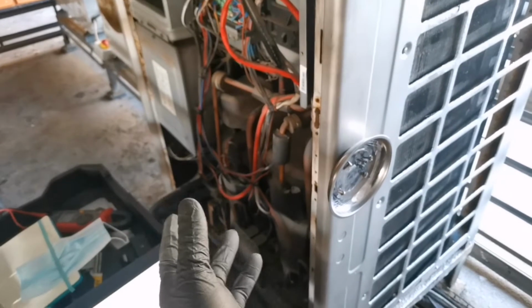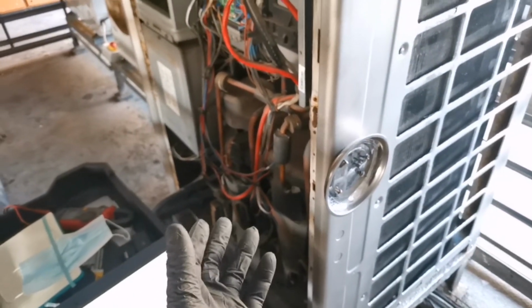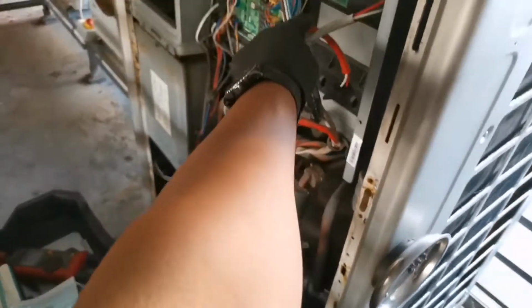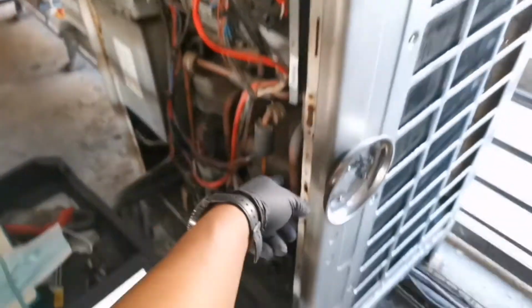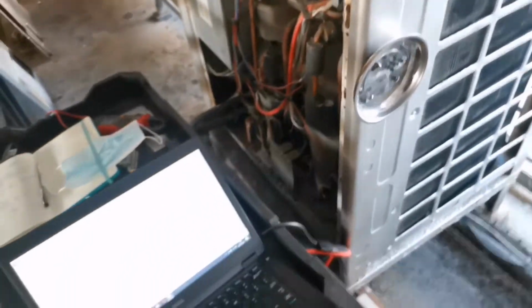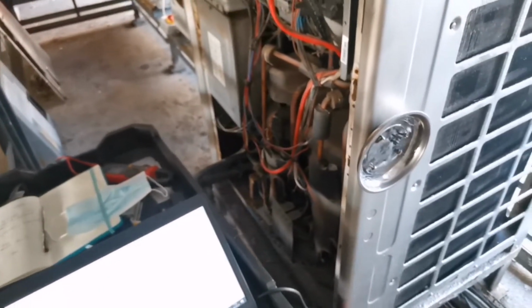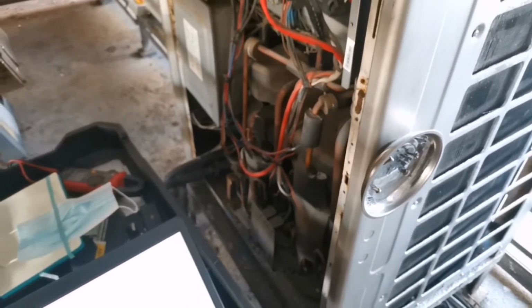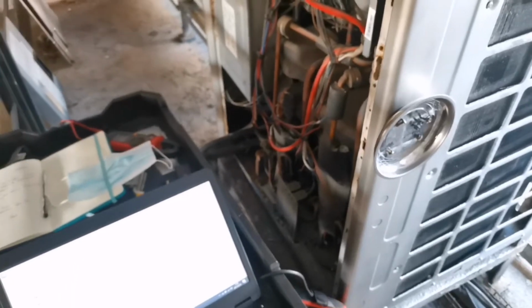So when they're using this system, for the first couple of minutes it seems as if there's nothing happening because that compressor has been disconnected. So only once compressor 2 kicks on, there's some cooling happening on the inside. I've checked the data, it doesn't look bad, so for now they are up and running, but we're going to end up having to change that.